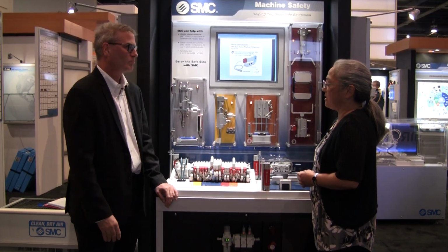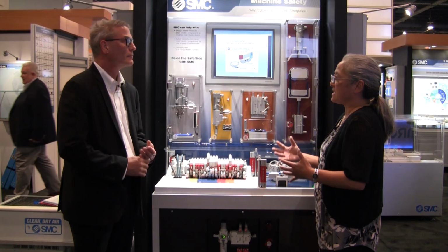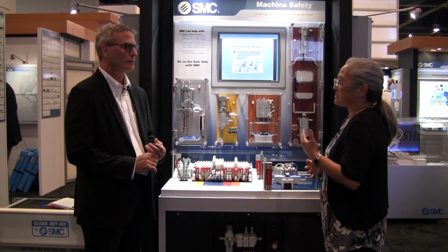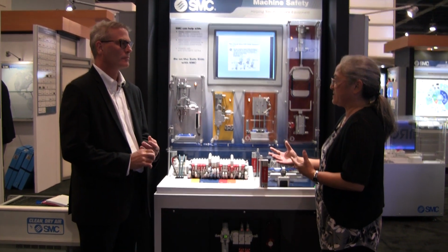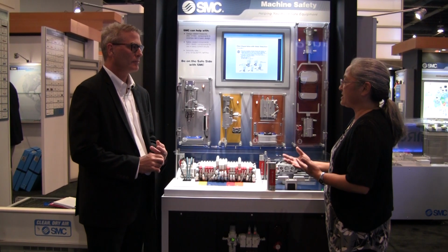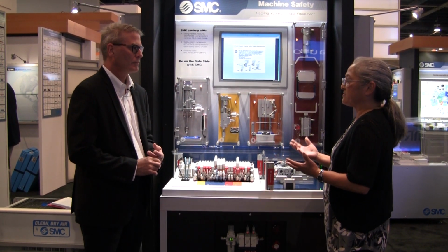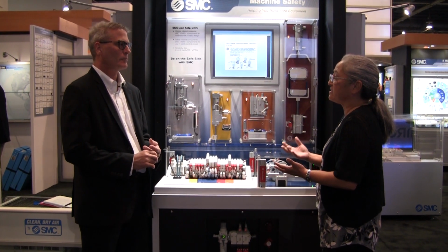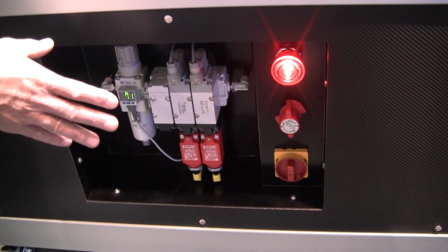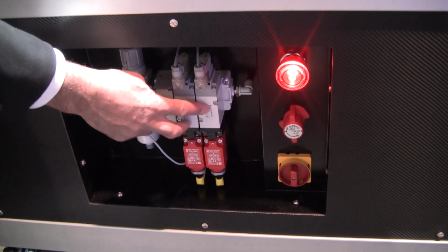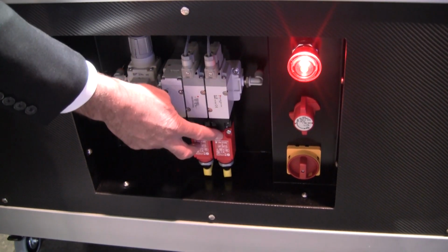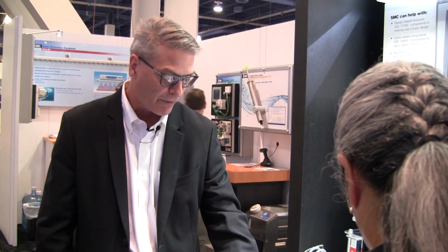Okay. And when you go through the risk assessment, safety functions would probably be something that would be looked at. What are some examples of safety functions that we could solve in the pneumatic world? Well, the traditional method is to do a full e-stop, which is something like this. We would vent the entire system. We're using a 2-channel valve, which has redundancy built into it, as well as reporting or feedback.